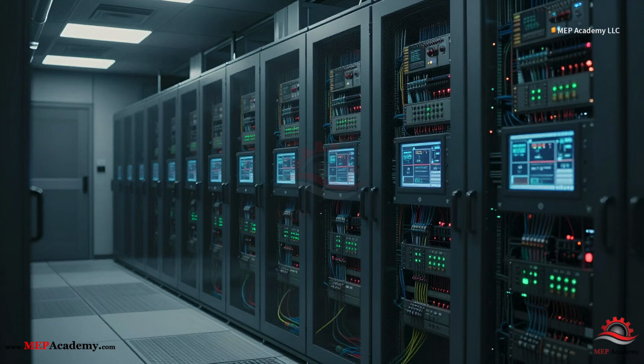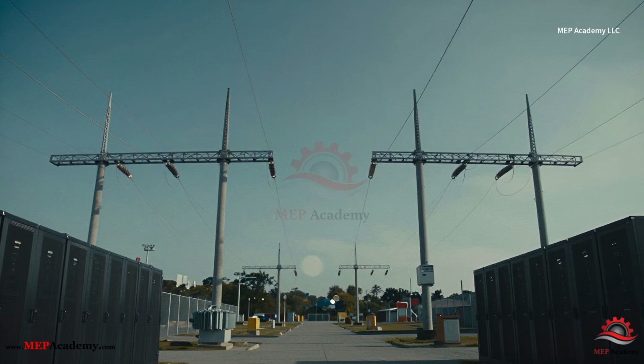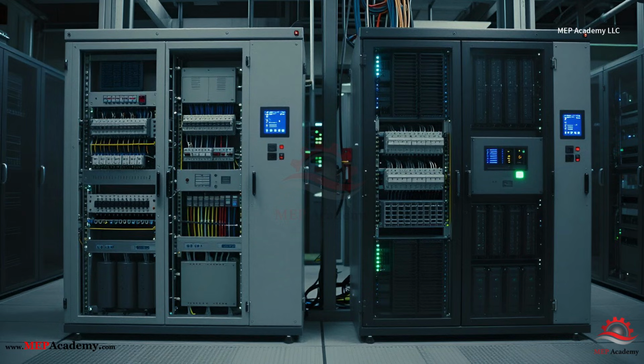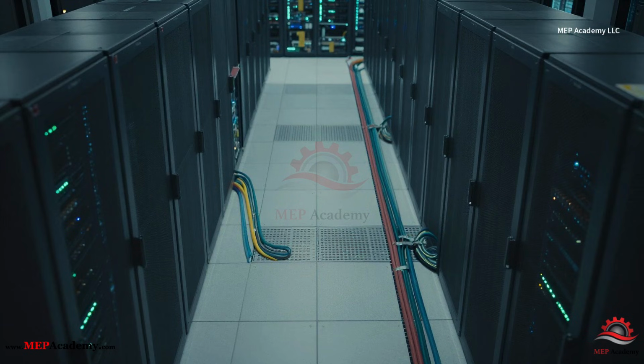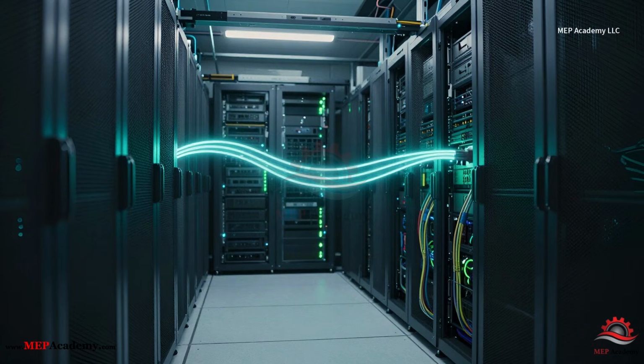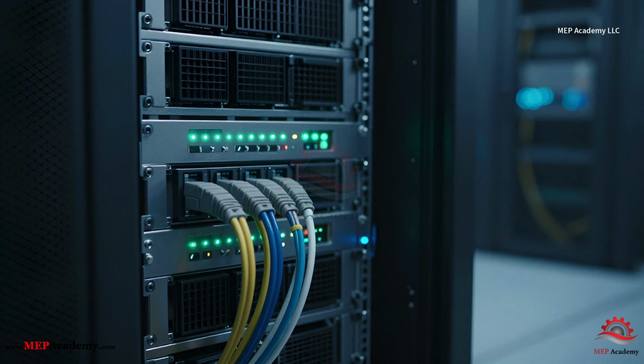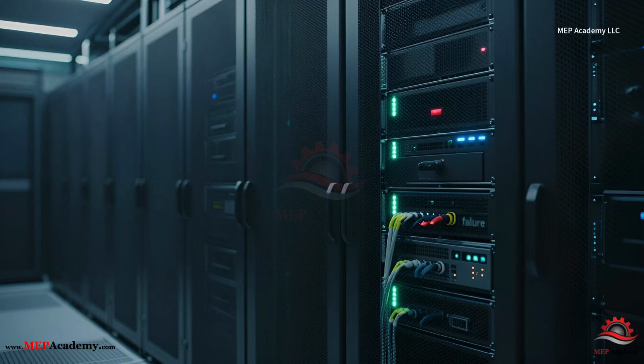Electrical systems often use 2N architecture as well. A 2N electrical system might include 2 independent utility feeds, 2 separate switchgear lineups, 2 UPS systems, and 2 power distribution paths to the server racks. Each power path is capable of supplying 100% of the load. Servers are often connected to both electrical paths using dual power supplies, allowing them to continue operating even if one power path fails. This architecture dramatically increases reliability.